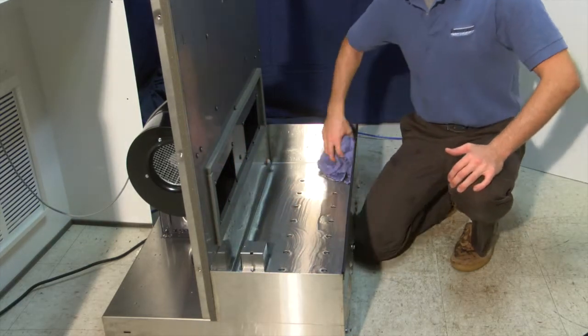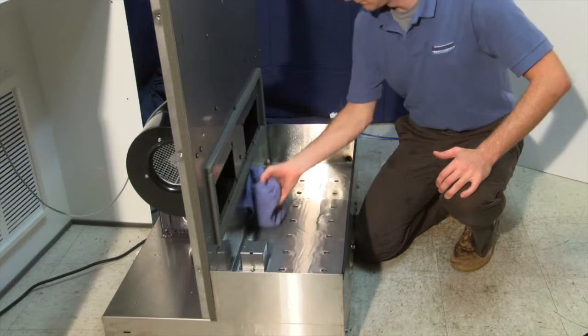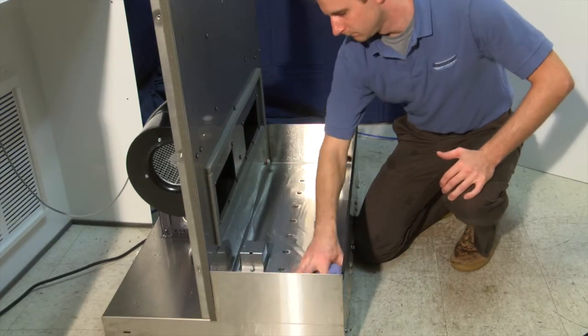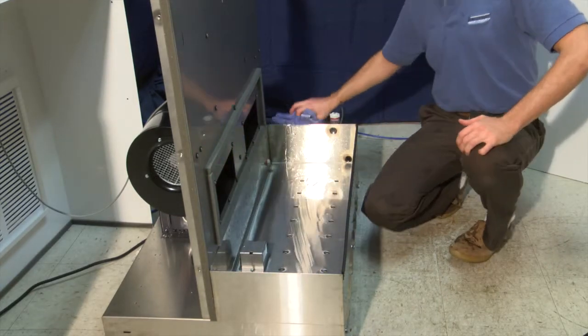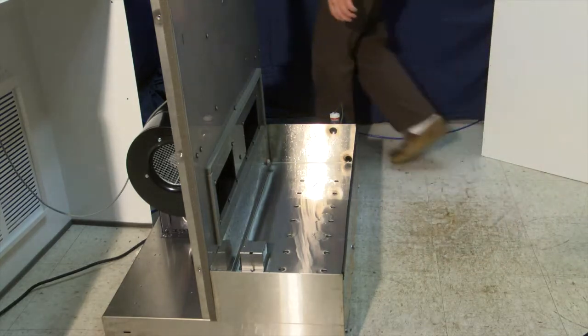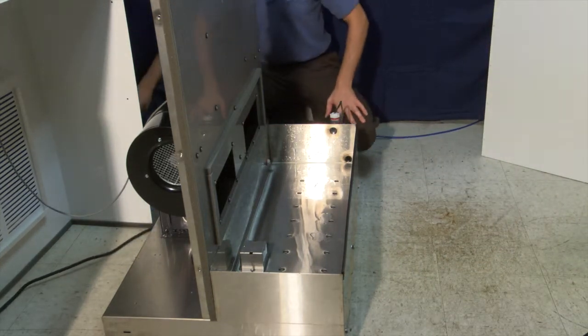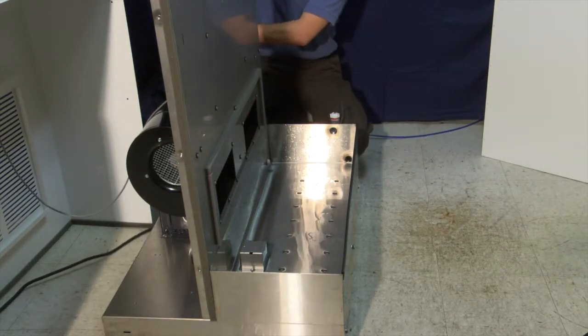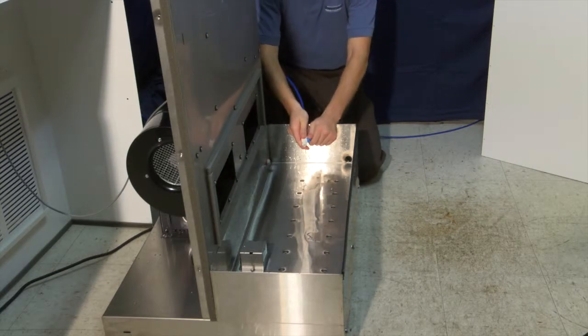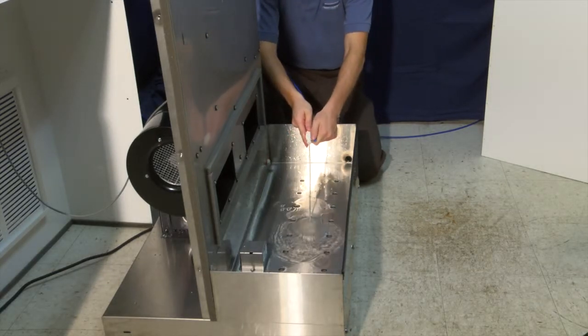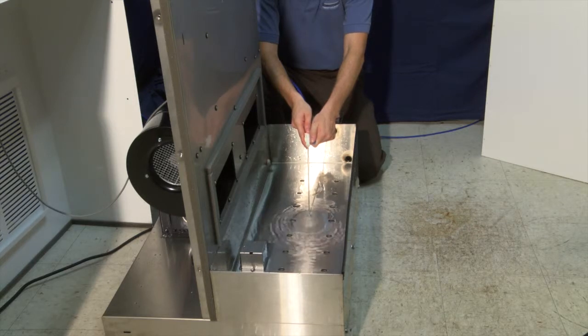You also do not want to scratch or scrape the transducers themselves. You can let the bleach or alcohol solution set on them for a short time and flush them out with fresh water. After cleaning the unit, prime the transducers with about an inch of water, just like at startup. You can think of the water pan like in an aquarium.